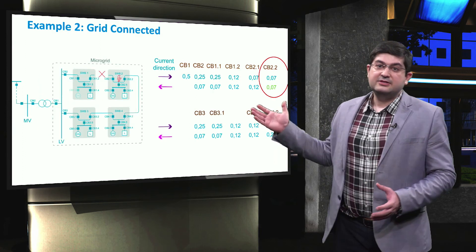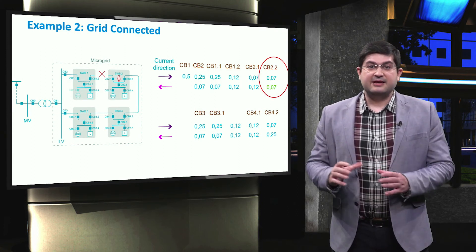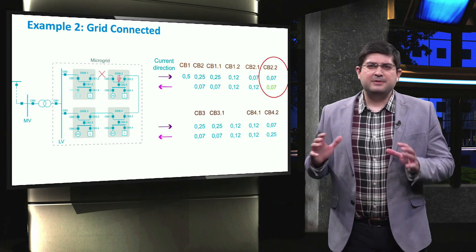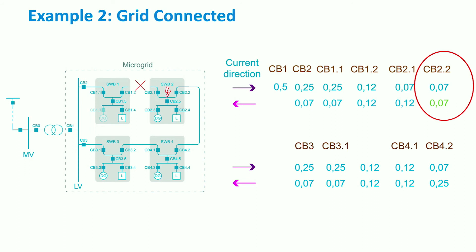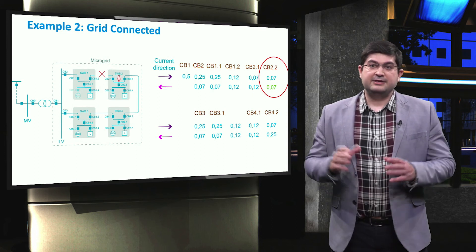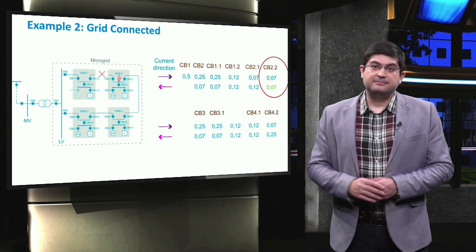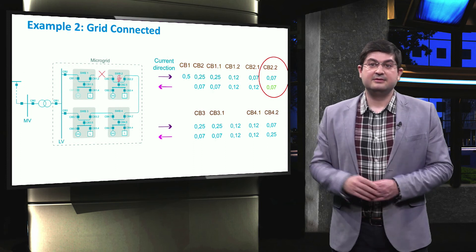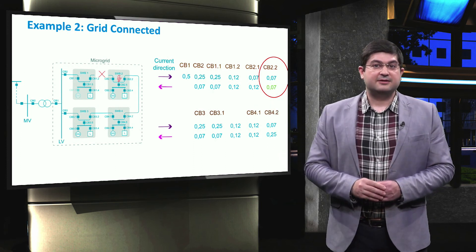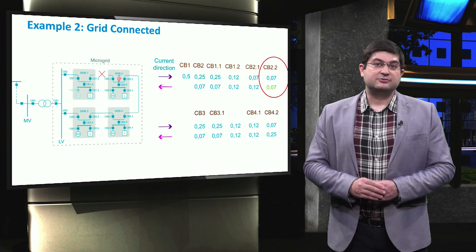To solve this selectivity issue, we employ adaptive protection. The main reason is that the configuration of the microgrid has been completely changed after the first fault. Therefore, all the relay time-current tripping settings shall be adapted to the new configuration. For this example, the time setting of circuit breaker 2.2 is changed from 0.25 to 0.07 seconds. Therefore, if circuit breaker 4.2 does not disconnect, circuit breaker 2.2 will disconnect faster than circuit breaker 4.1, avoiding the unnecessary disconnection of switchboard 4.